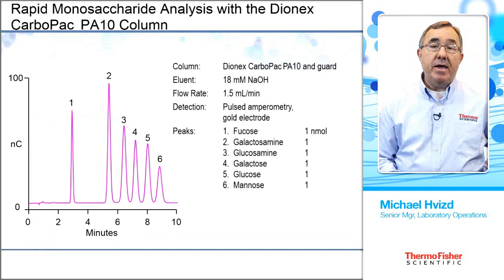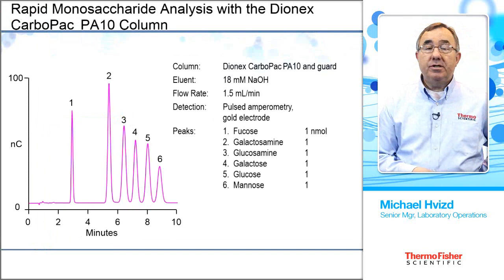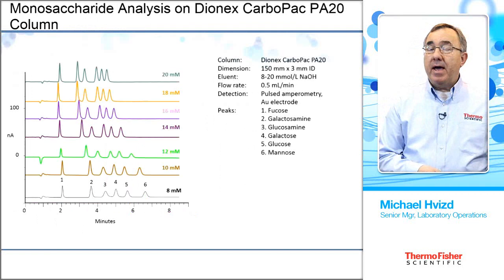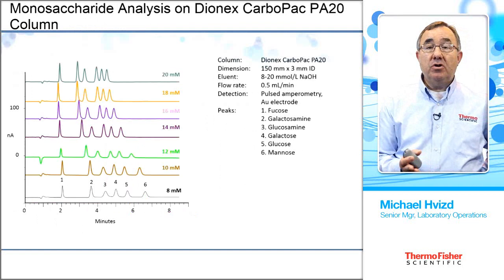Now let's go into some application examples. The first ones I want to show are classical separation techniques used for many years. Here we're using sodium hydroxide made up from 50% solution. This first example is the classical separation of the monosaccharides — we call this the mix of six, with two amino sugars in the group as well. This separation is very short, only about 10 minutes, running an isocratic eluent of 18 millimolar sodium hydroxide, using the Carbopac PA10 column.